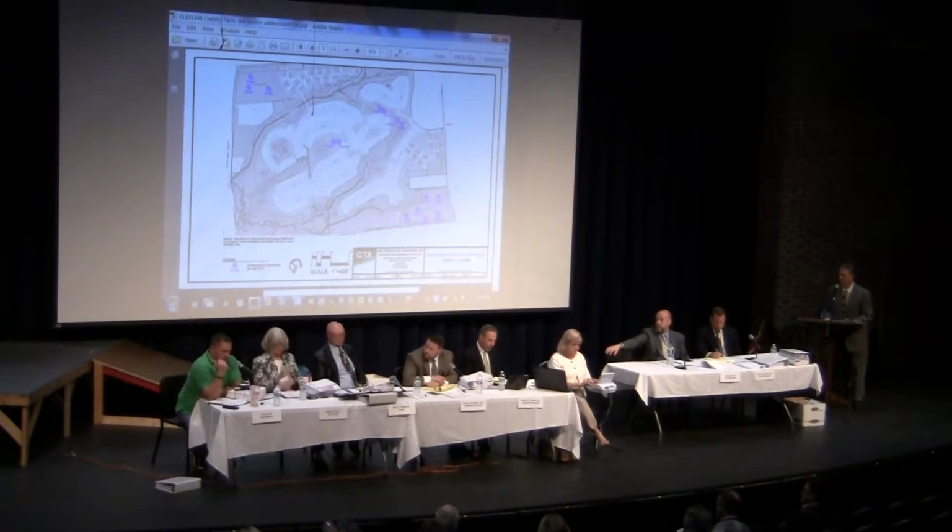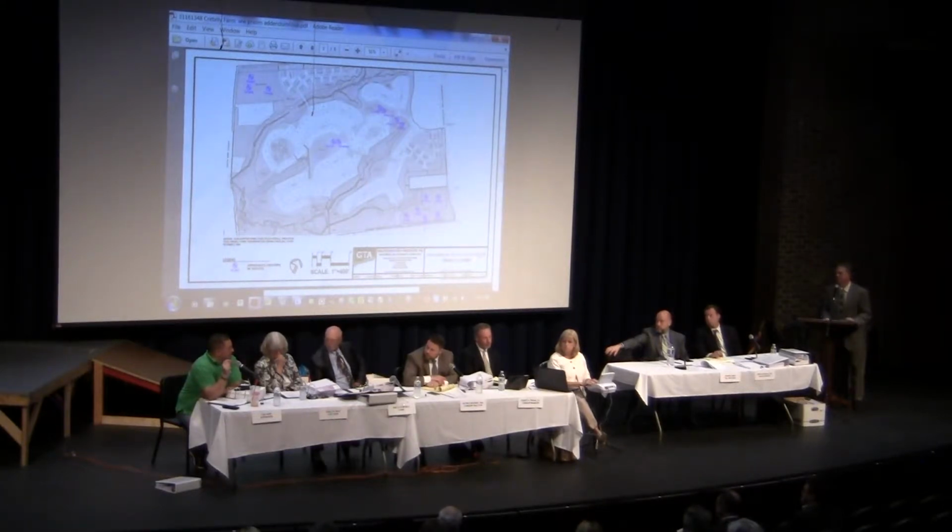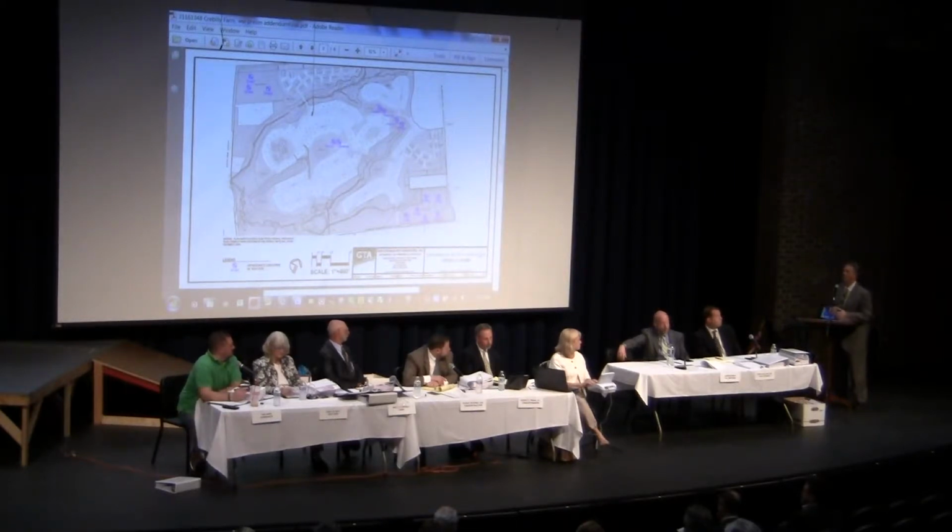Sure. Not that homeowners would do this, but I guess the concern with your daily flow rates is that it doesn't account for residents hooking their sump pump into the systems and things of that nature. What would that impact have on a drip irrigation system? Well, the actual wastewater production based on pump and haul of individual residents, and these are large Toll Brothers houses, is 146 gallons per day per house. So we designed it for 250.